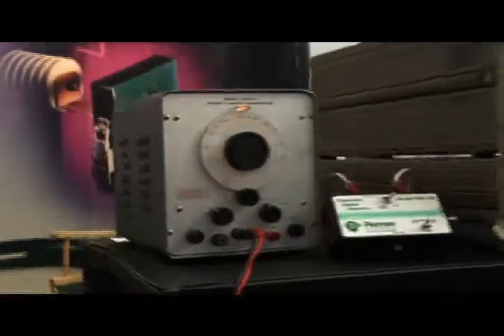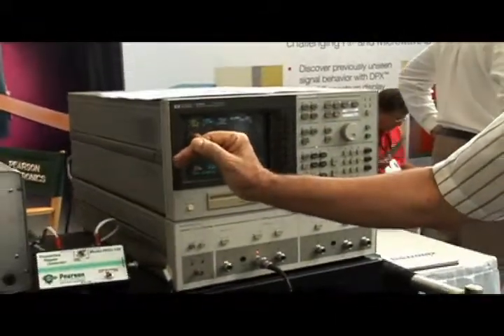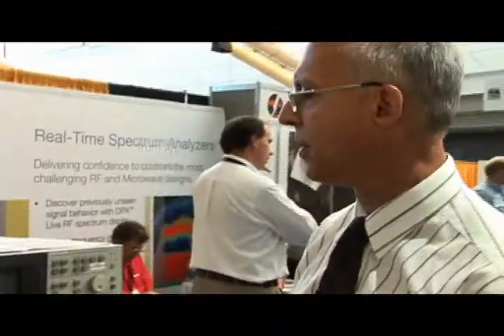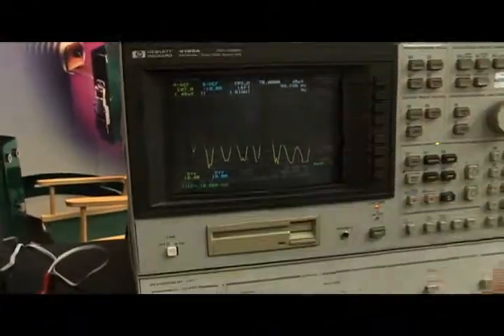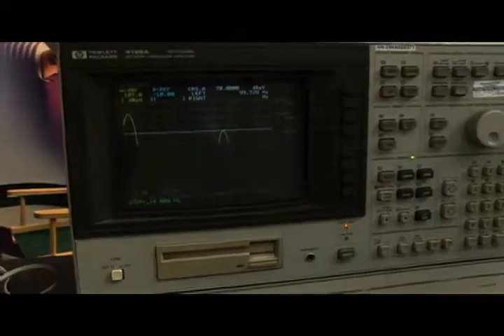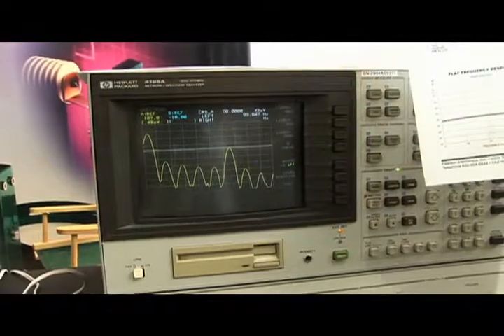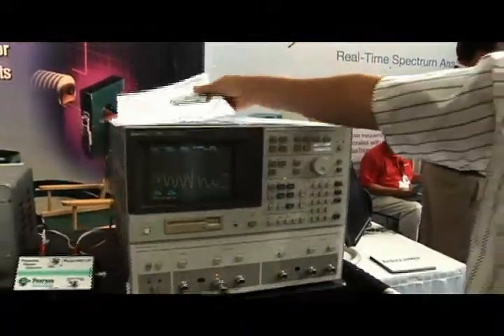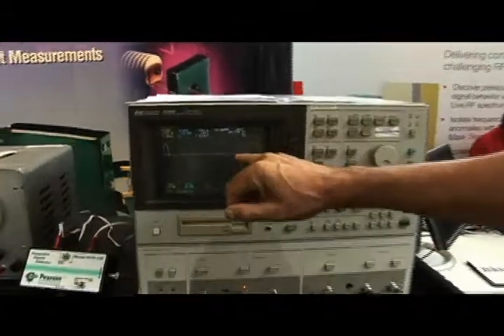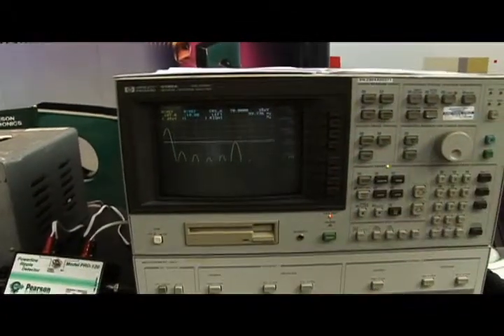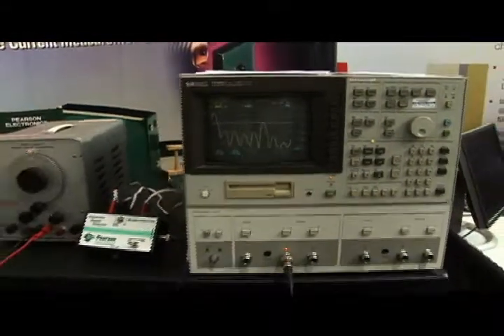But over here, using the Powerline Ripple Detector, we can look at this same signal — which used to be viewed on an oscilloscope — on a spectrum analyzer in the frequency domain. Here we're separating the powerline frequency of 60 Hz from the injected frequency, which is roughly 660 Hz. The white line here is the limit, and the limit is derived from the actual requirement by subtracting the transfer function of the device, which is 66 dB, from the limit — arriving at a 70 dB microvolt cursor. Now it's abundantly clear and very obvious that we are injecting at the limit. It's much easier to determine when we're at the limit.